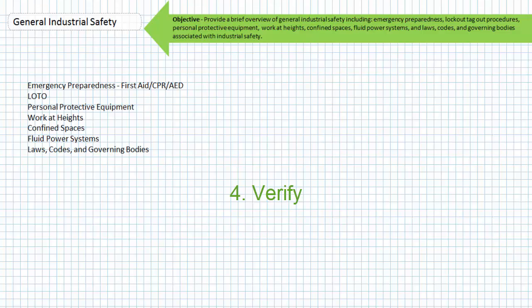Don't just assume things are safe before you begin work. Step 5: Now that you've verified the lockout and tagout procedure was successful, you can perform the service. Step 6: Once the procedure has been performed to your satisfaction, you can start cleaning the area and notify affected personnel you'll be returning the equipment to service. Now you can begin removing the lockouts and tagouts.